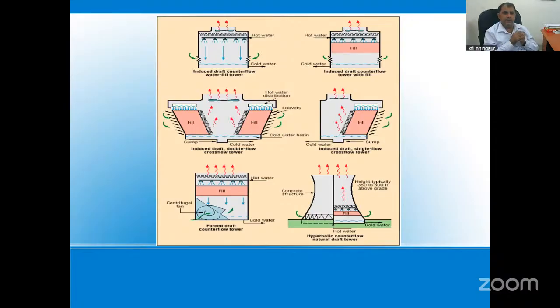It is a simple phenomenon. Now the next one is the induced draft double flow cross flow tower. Double flow means there is hot water distribution on both sides of the induced draft fan. Water enters at the top of the cooling tower and circulates, passing by the fill zone area. Here is the fill zone area where the droplets spread out and increase the surface area. Here the air contacts the hot water.